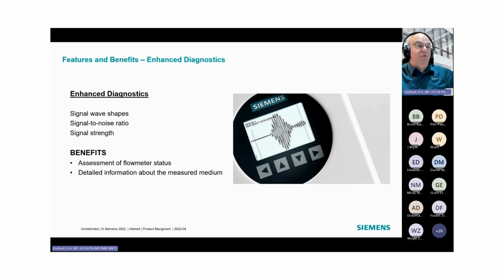And what that helps you do is get information out of the pipe. So if you're looking at your diagnostic screen and you're not getting good information, you can set the device for a multiple traverse mount and move the transducers further away. The transmitter will tell you how far they need to be to get enough information for, say, a challenging gas like helium or hydrogen. There's not a lot of material there to slow the signal up, so you would have multiple bounces in order to get the signal through. Again, I don't feel like I've answered that question appropriately, but I'm going to give you all my contact information in a couple of slides, and you can email me or call me directly, and we'll talk more.